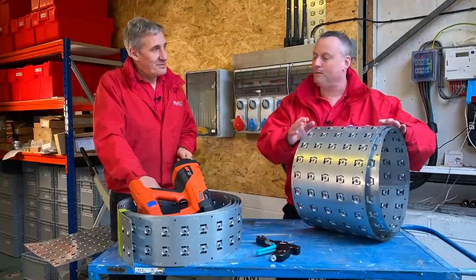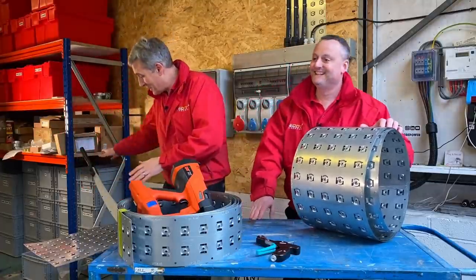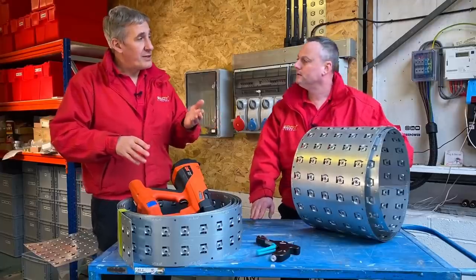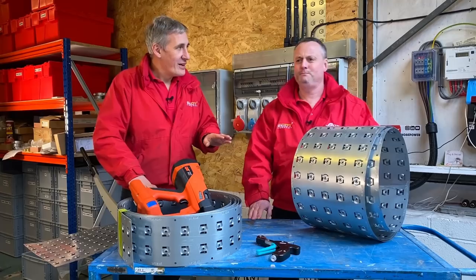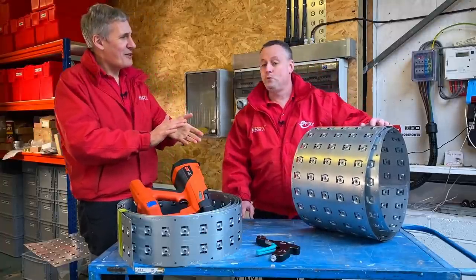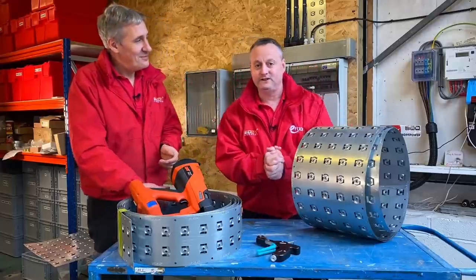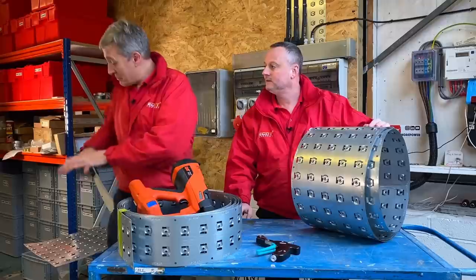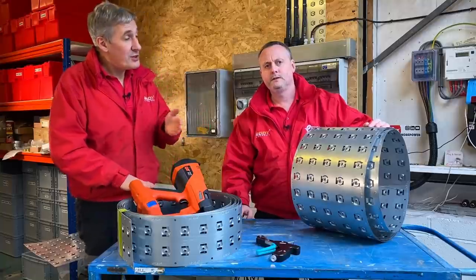If you've got a 15-meter roll and don't need all of it, you'll need to cut it to length. Along with the roller tray we also got a special guillotine - you could use a traditional angle grinder or jigsaw, but the advantage of the guillotine is there's no dust. In that initial data center application, a lot of computer equipment is involved and people in that industry get very nervous about dust - it gets into the server. You'll also find something called zinc whiskers in that industry. The tray is pre-galvanized, so you don't get zinc whiskers, though that does limit it to indoor applications.